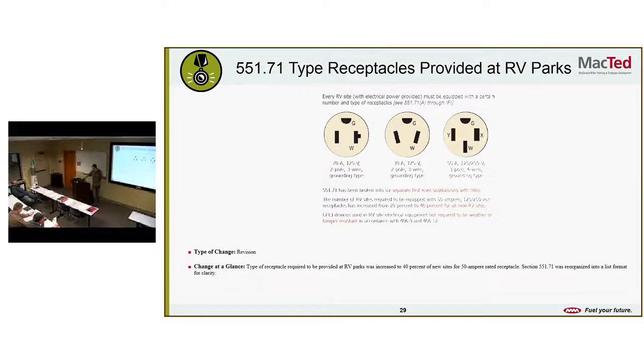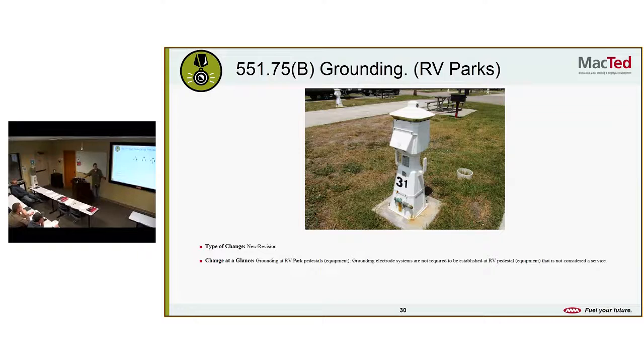Type of receptacles provided at RV parks. Oh, for you RVers out there. The type of receptacle required to be provided at RV parks was increased to 40% of all new sites for 50 amp rated receptacles. Yeah, it was reorganized into a list format for clarity. So as everybody's RVs are getting bigger and bigger, now they're saying 40% of your outlets need to be 50 amp receptacles. See on a 20 amp. Yeah. So that's good for everybody with a larger RV. Be able to have all the power you want.